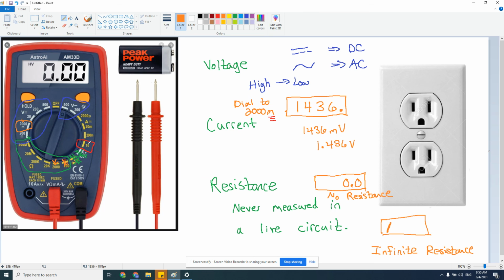Again, with resistance, starting high and dialing down is optimal, though it's not as big a deal since you're not in a live circuit—so it's not as important for safety. It's very difficult to damage the meter when measuring resistance. The number one way you could damage it is by measuring resistance in a live circuit—you never want to do that. You physically shut off the power, remove the item you want to measure, measure the resistance, then put that item back into the circuit and turn it back on.